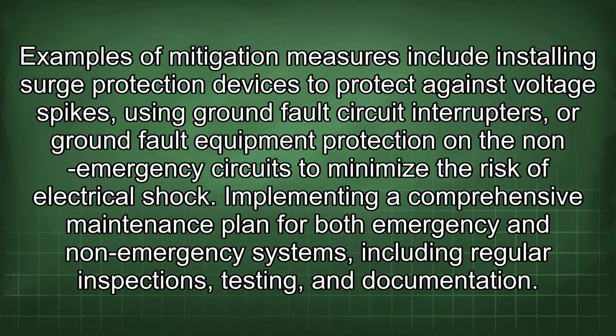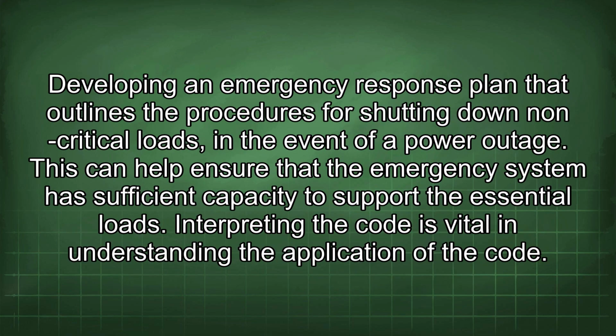Examples of mitigation measures include installing surge protection devices to protect against voltage spikes, using ground fault circuit interrupters, or ground fault equipment protection on the non-emergency circuits to minimize the risk of electrical shock. Implementing a comprehensive maintenance plan for both emergency and non-emergency systems, including regular inspections, testing, and documentation. Developing an emergency response plan that outlines the procedures for shutting down non-critical loads in the event of a power outage. This can help ensure that the emergency system has sufficient capacity to support the essential loads.